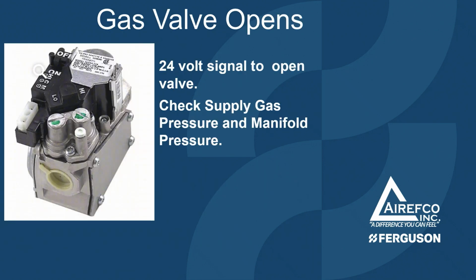The next thing that will happen is the gas valve will open. There is a 24-volt signal usually to open the gas valve. Make sure you check the supply gas and the manifold pressure to make sure there is sufficient pressure there for the gas valve to operate.